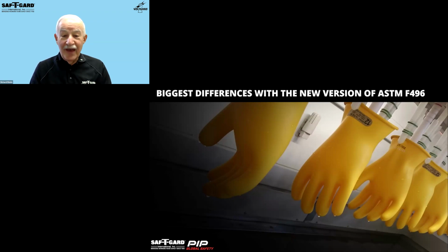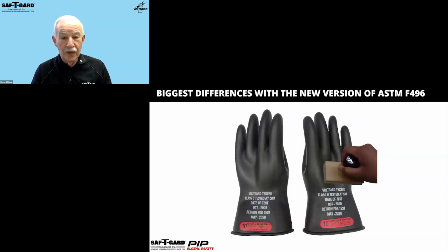This dielectric test is actually twofold. It's pass-fail on the ability to withstand the rated test voltage, and for rubber gloves, it's also quantitative on the ability of the rubber material to minimize electrical current passing through the rubber gloves above the maximum contained in the specifications. It's a unique machine, and you're welcome to visit us anytime or see some of our videos as to how this works. The rubber insulating gloves are tested by filling them with water and then immersing them in water and applying the test voltage.